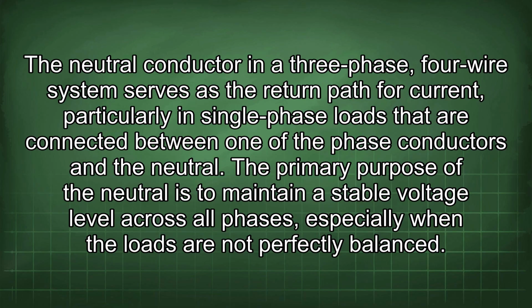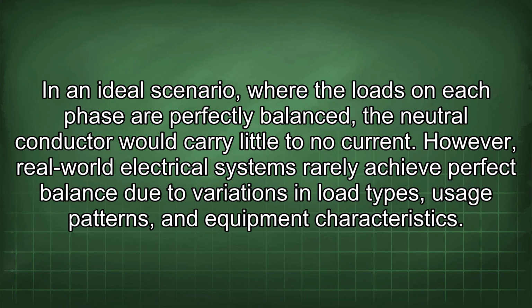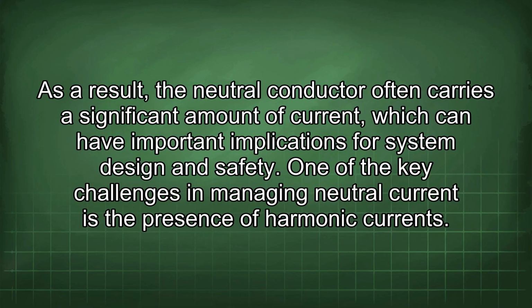The neutral conductor in a three-phase, four-wire system serves as the return path for current, particularly in single-phase loads that are connected between one of the phase conductors and the neutral. The primary purpose of the neutral is to maintain a stable voltage level across all phases, especially when the loads are not perfectly balanced. In an ideal scenario, where the loads on each phase are perfectly balanced, the neutral conductor would carry little to no current. However, real-world electrical systems rarely achieve perfect balance due to variations in load types, usage patterns, and equipment characteristics. As a result, the neutral conductor often carries a significant amount of current, which can have important implications for system design and safety.